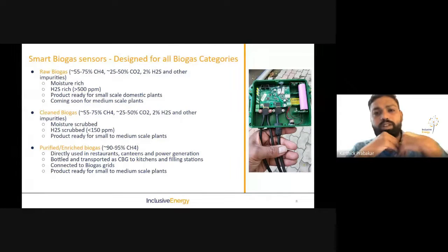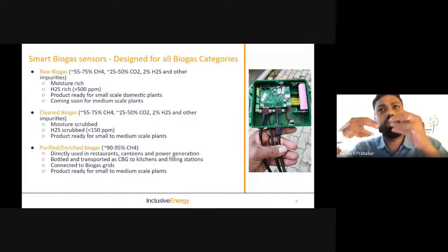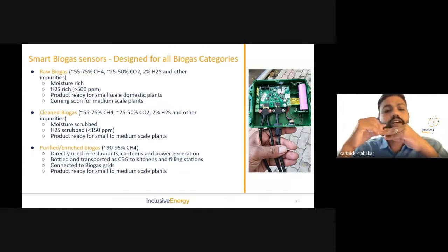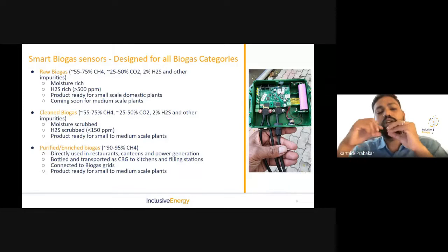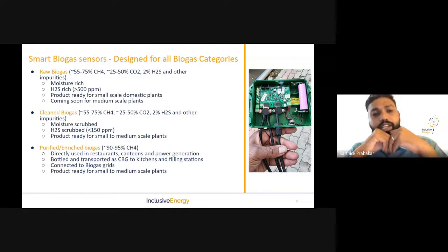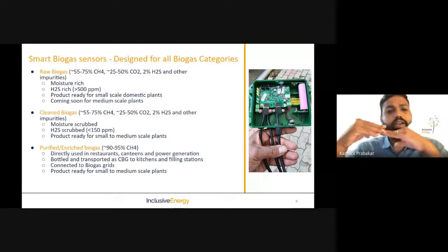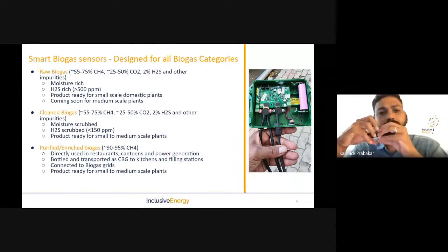These sensors are designed for a range of biogas compositions. For example, raw biogas, which has 55 to 75% methane and a high percentage of carbon dioxide and H2S as well, and is always rich in moisture and H2S. We have a product ready for this segment in the small scale domestic plant sector, and will be coming soon with a product that will also cater to medium scale plants for raw biogas. Clean biogas is nothing but raw biogas, but used in systems where there is a system for scrubbing the moisture and H2S to a certain extent, so that it's not very hazardous in terms of what's passing through the pipeline.